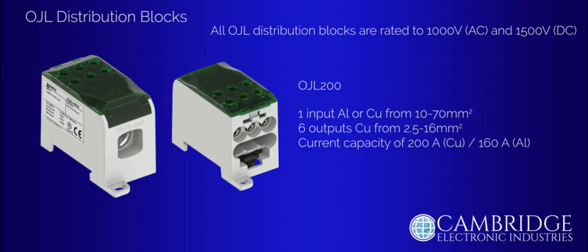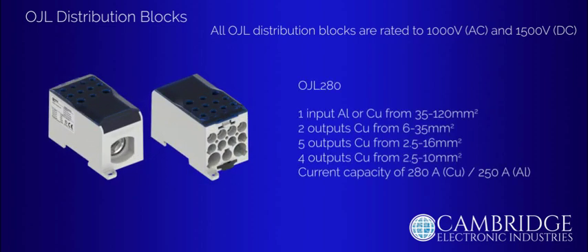The OJL 200 has a single input which accepts from 10 to 70mm square copper or aluminium cable and offers 6 outputs of copper cable from 2.5 to 16mm square. The overall current capacity of the OJL 200 is 200 amps for copper cables and 160 amps for aluminium cables. They are available with transparent black, blue and green covers. The OJL 280 is a single distribution block for branching connections and distributes the current through 11 output cables in varying formats. Its maximum current capacity is 280 amps for copper cables and 250 amps for aluminium cables.